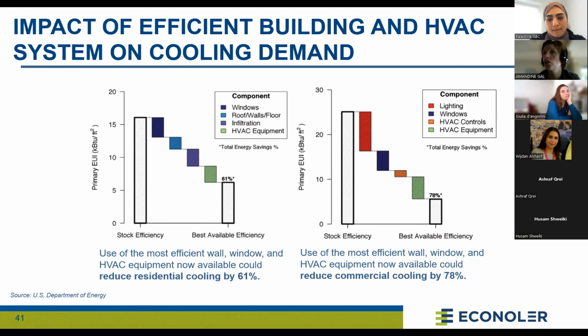And then just for the HVAC system, you see that combining both also gives you a huge impact. Meaning the total energy saving, if you implement such measures only on lighting, windows, and HVAC, not talking about insulation of roof and so on, but just taking this, if you use the best available efficiency system on the market, you can have around 80% energy saving, which is huge.